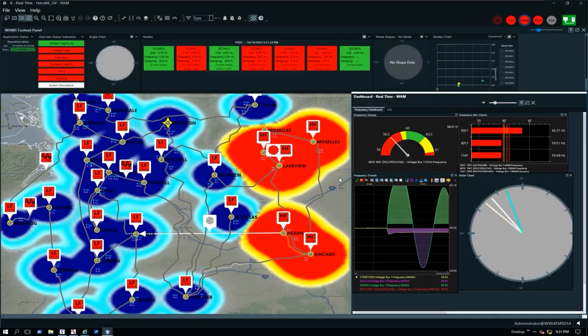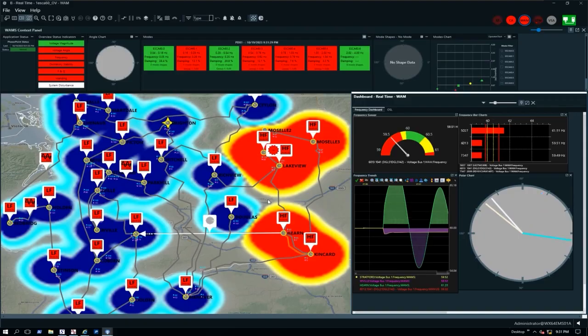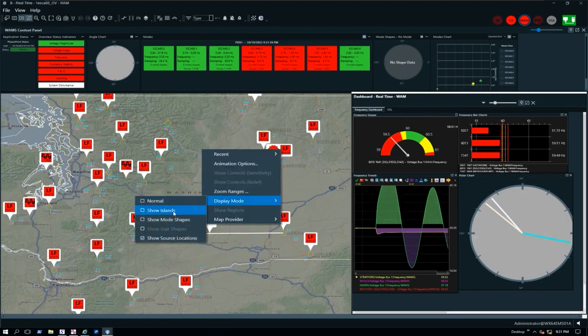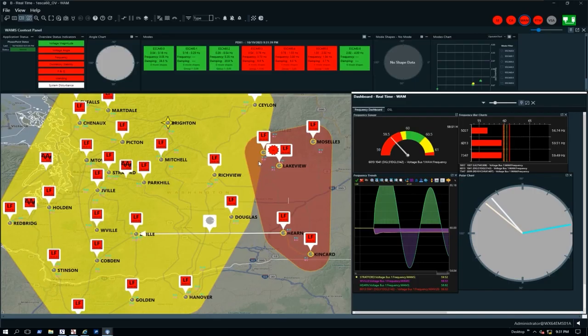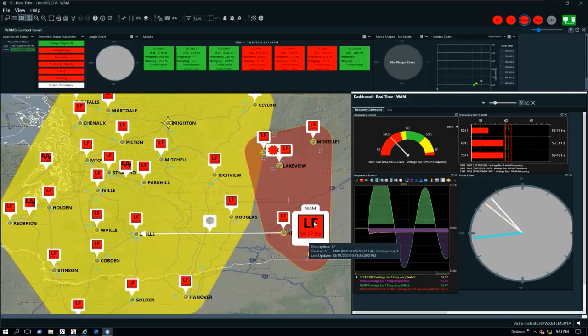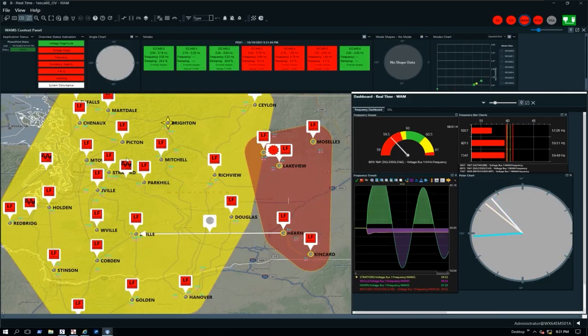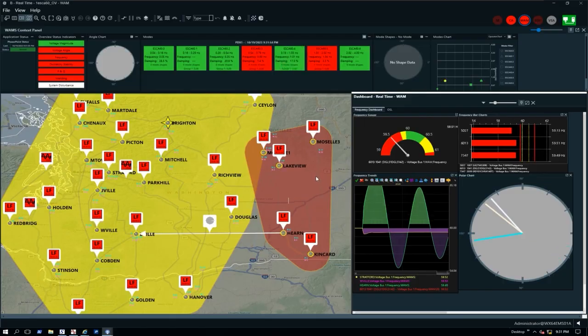As you saw, whenever the frequency swings low, everything turns blue, so it's hard to tell which islands are which. So we have a visualization showing the islands on the system. It's a help to your system operators to show you exactly which substations, which generators, which load, are in island 1 or island 2. And that's going to make sure that they're acting on the correct generators or loads to get the frequencies balanced between these two.